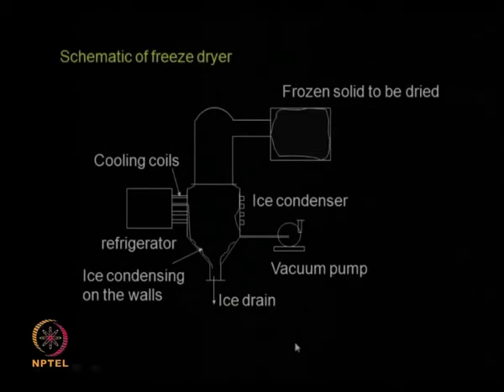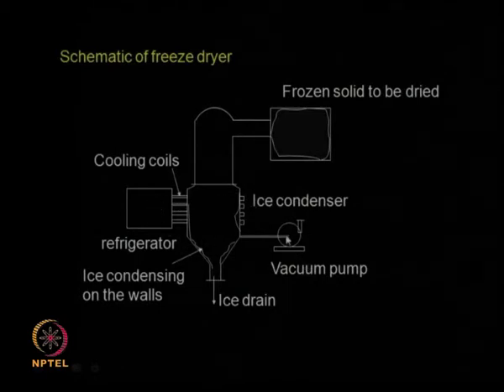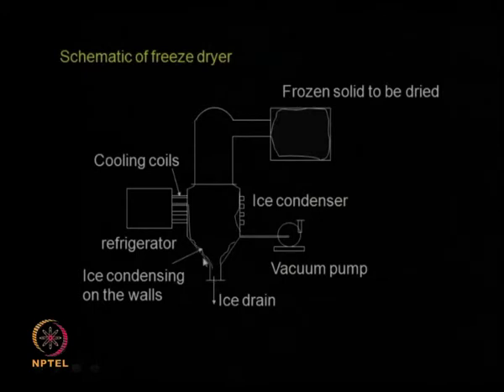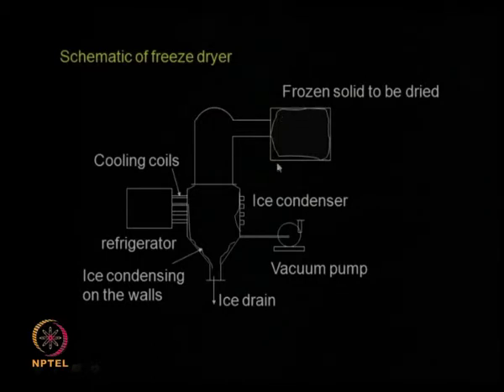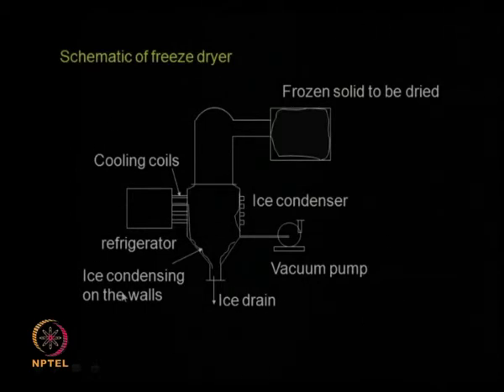A schematic of a large-scale industrial freeze dryer: frozen solid in a big container needs to be dried. Water has become ice. There is a refrigeration system and a vacuum pump. The ice becomes vapor, travels down and condenses — forming ice on the wall again. The vacuum pump provides the required vacuum while the temperature is high enough for ice to go directly into vapor, which is condensed and collected. The refrigeration system keeps the surface temperature low. That is how a large-scale freeze drying unit works.